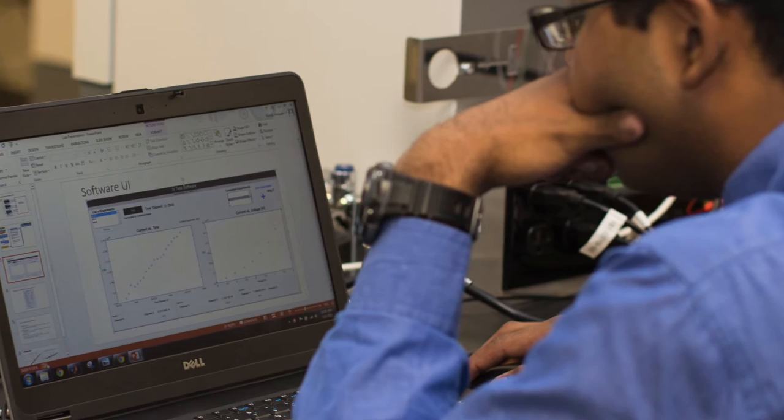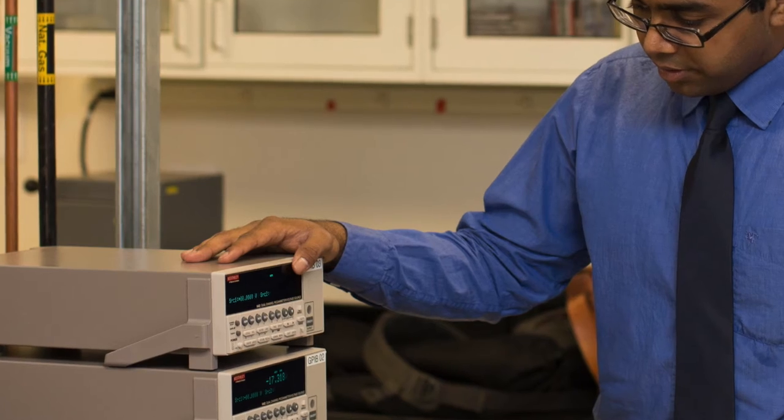The research I'm doing here involves the development of software for performing leakage current experiments. What leakage current testing is, is testing the insulation that goes in a neural electrode.